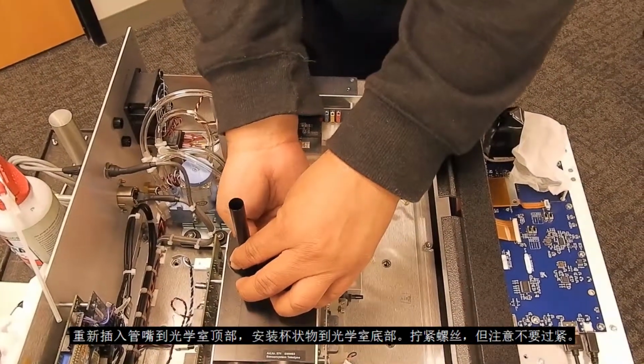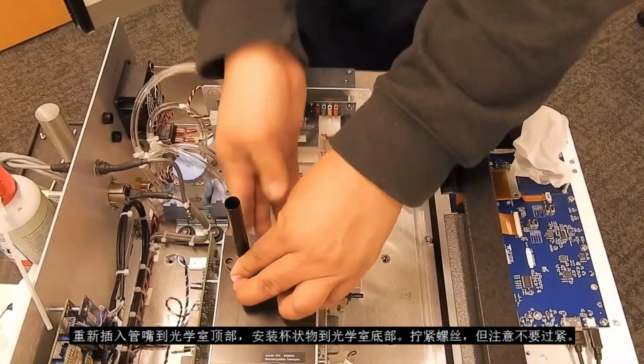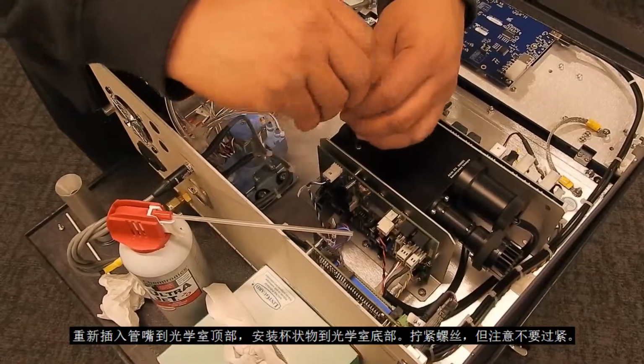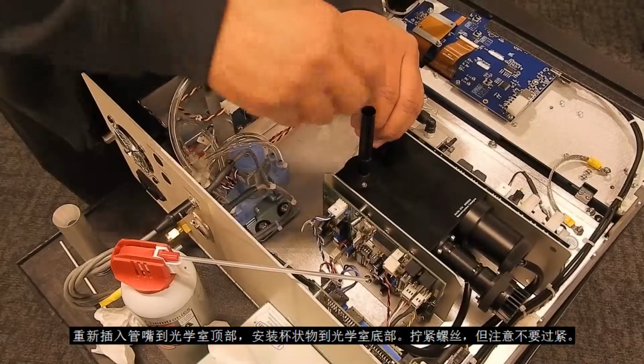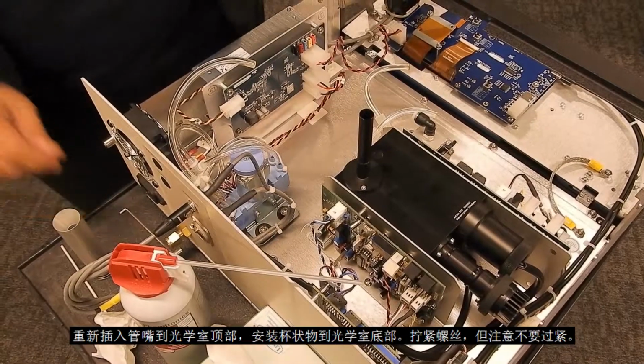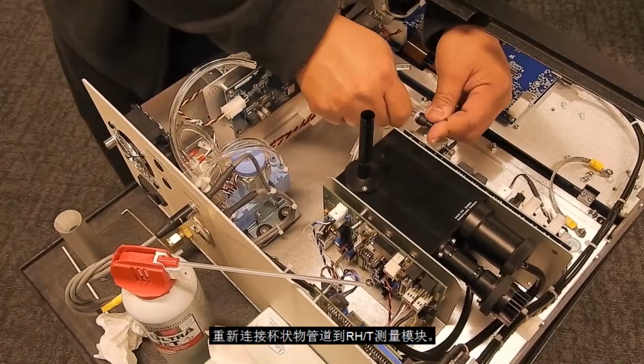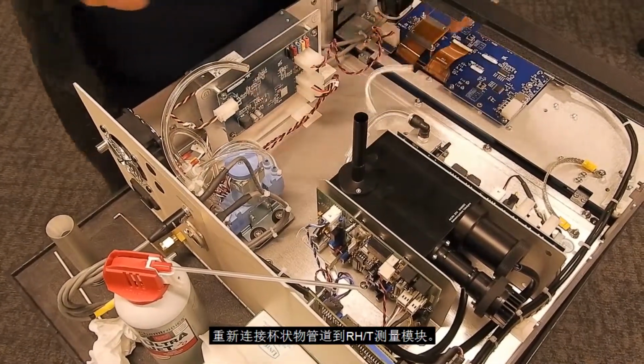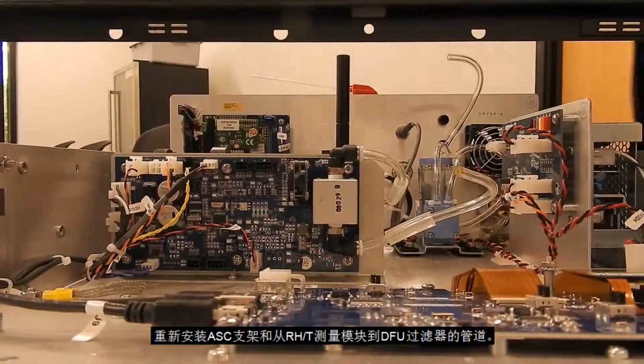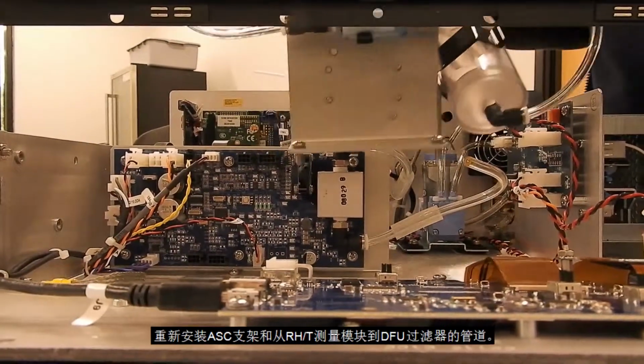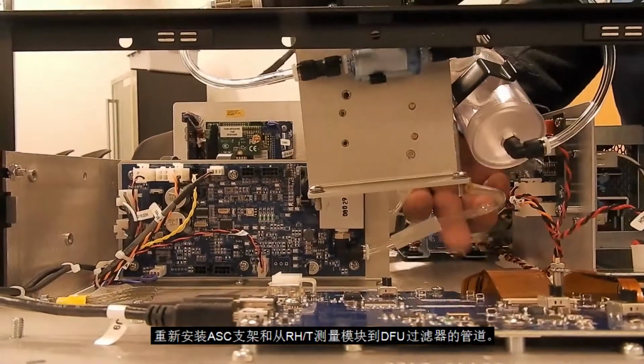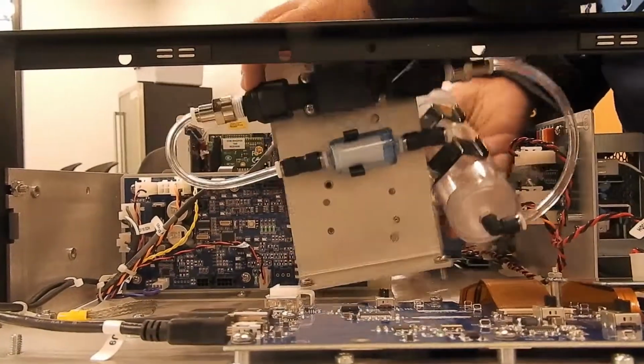Reinsert the nozzle to the top of the optical cell. Install the cup in the bottom of the optical chamber. Tighten the screws to hand tight. Caution: do not over tighten the screws. Reconnect the tubing from the cup to the RHT sensor. Reinstall the ASC support and the tubing from the RHT sensor to the DFU filter.